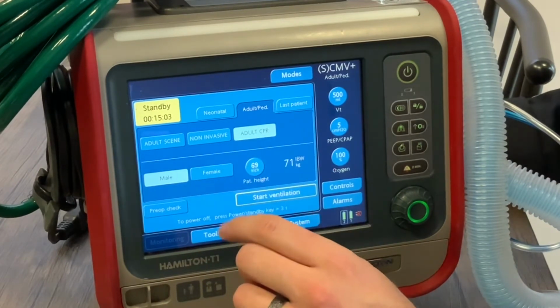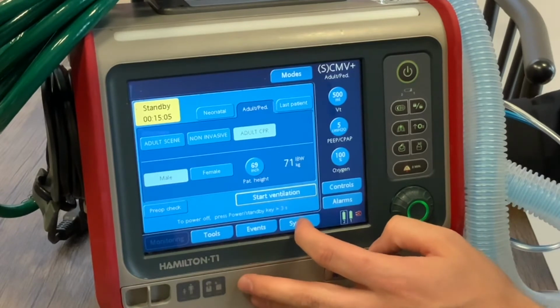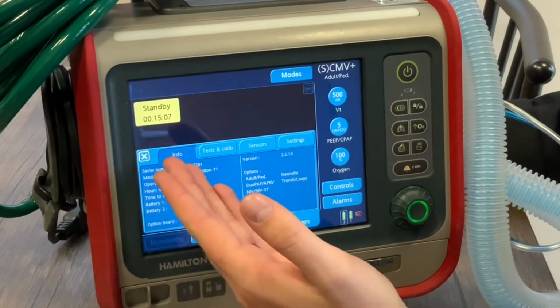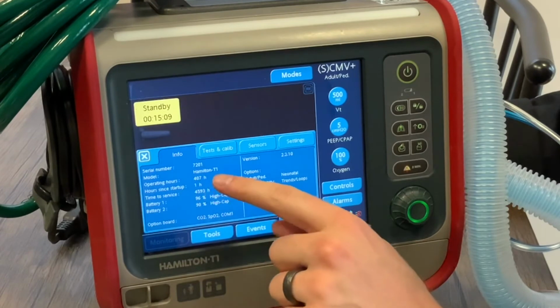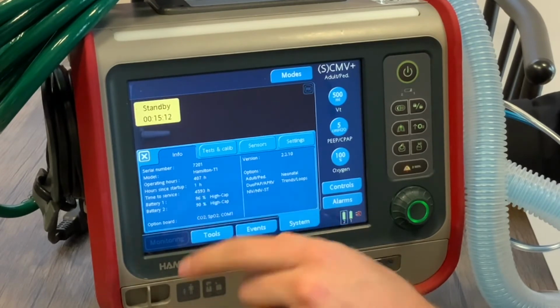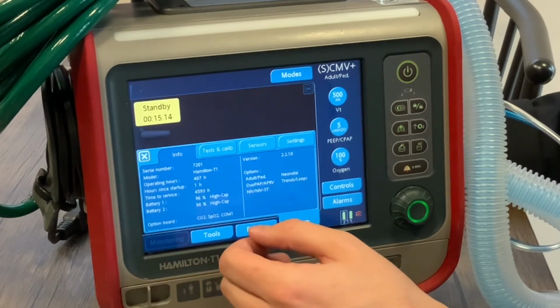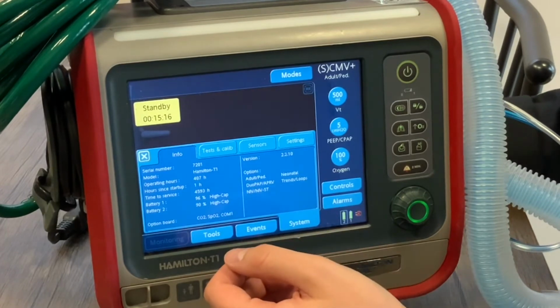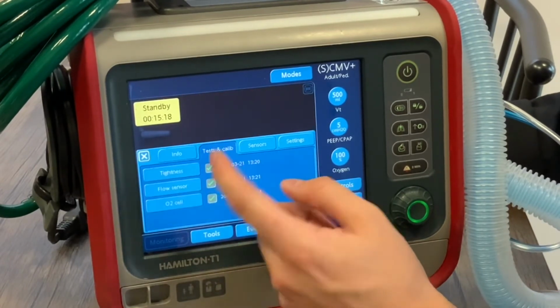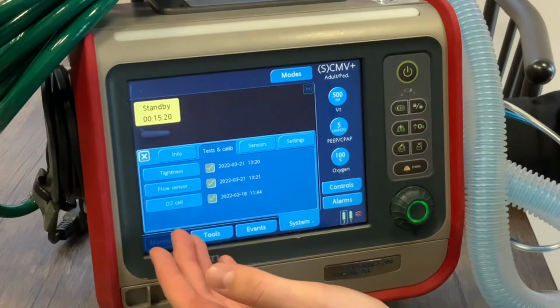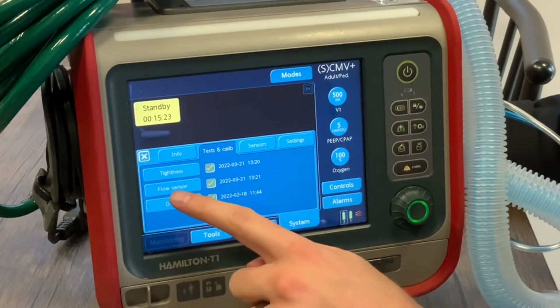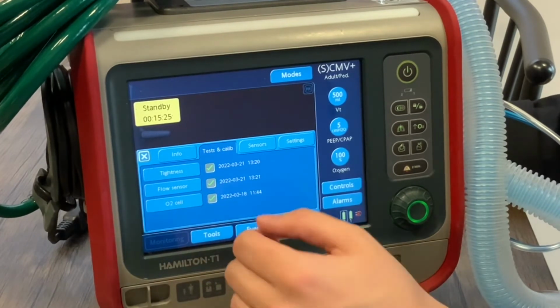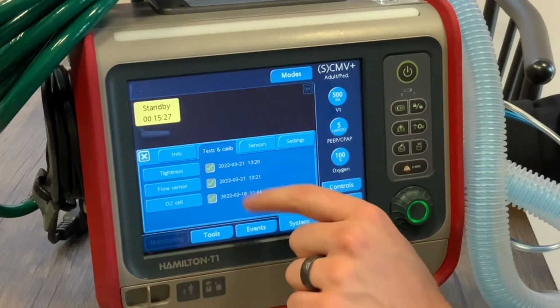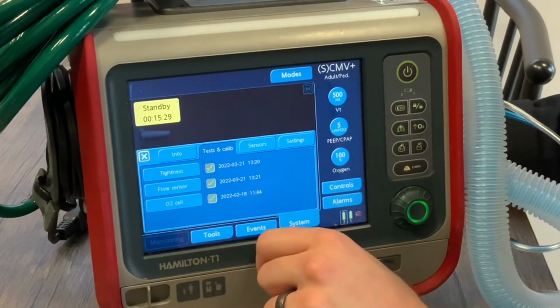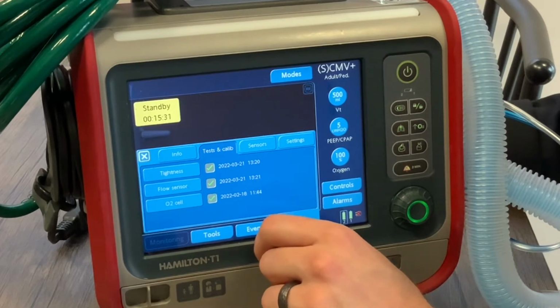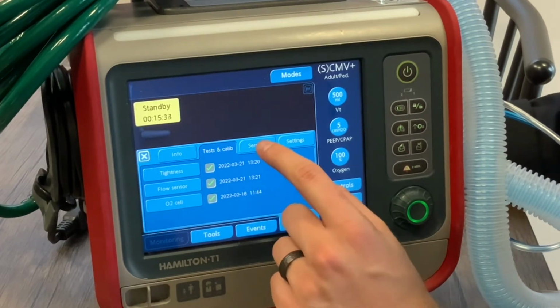It knows. If we press system, it gives us the info: the serial number, the time, the hours used, the hours left to PM, capacity of the batteries, and all the options we have selected. Test and calibrations shows us the preoperative checks: tightness check, flow sensor check, O2 cell. Again, we'll get to those in a second, and the last time they were performed. The green check mark indicates that the test was passed. A red X would be shown if the test had been failed.